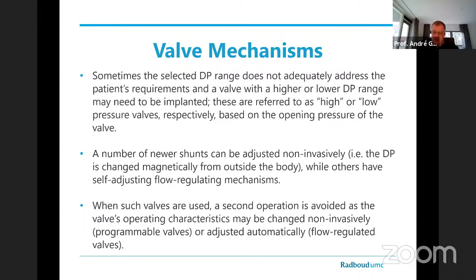Typically, if you look at the available shunts, they are delivered in 3 to 5 ranges: low, medium, and high pressure, and some offer very low and very high also. These are fixed. The problem is that there are no voluntary industry standards on how to measure pressure or flow characteristics of a shunt. Every manufacturer does it by himself or herself. And any standards that have been described have never been adopted universally. And now it comes: there are not even industry-defined values for each of these ranges. So if you have a medium pressure valve from one manufacturer and a medium pressure valve from another manufacturer, they could have completely different opening pressures. That makes it really difficult.